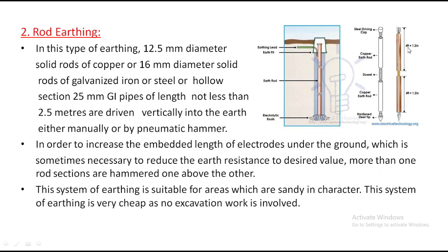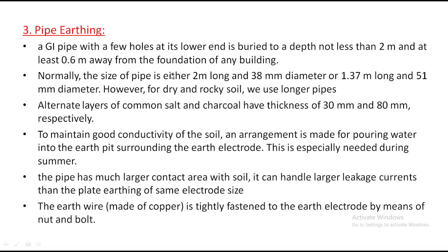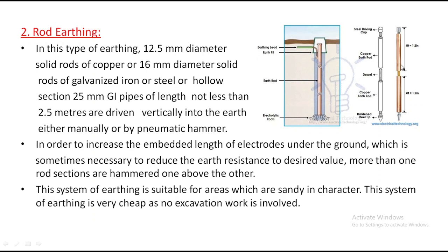Generally this length will be 4 feet, 1.2 meter, and this is also 4 feet. Like this we have to use it. Look at here, 1.2 meter, 4 feet, and this is also 1.2 meter. The earthing will be given to this rod. Whenever a short circuit of the metal or outer part occurs, the current will automatically flow through this rod and enter into the ground. Then the machine will be safe.